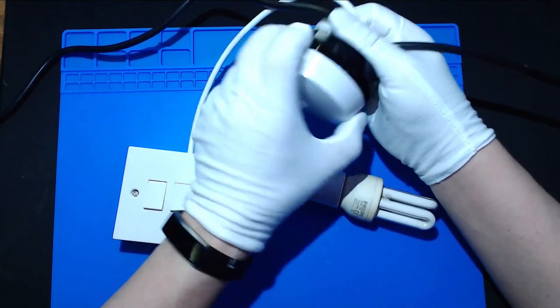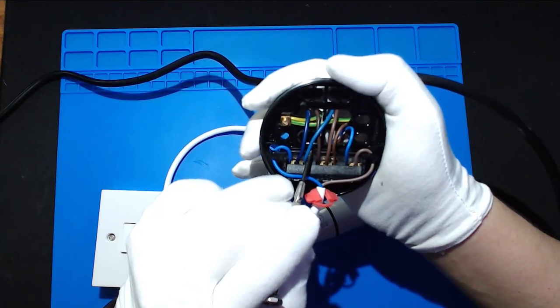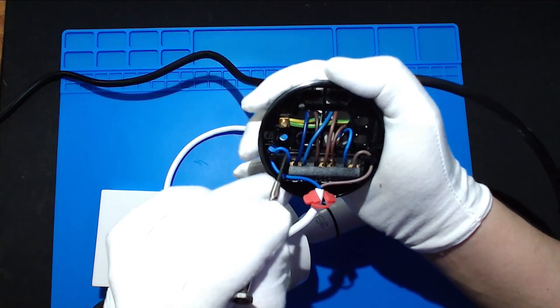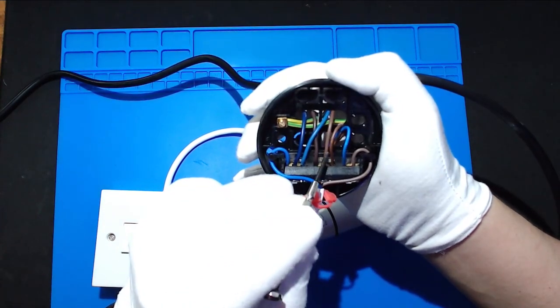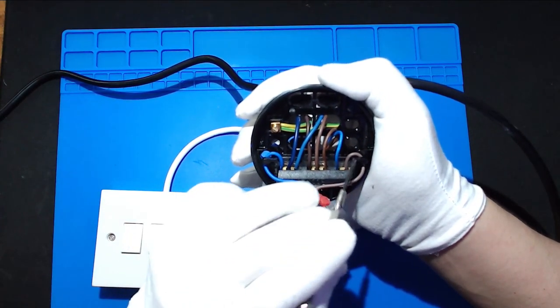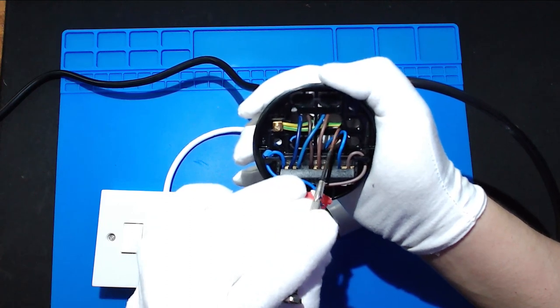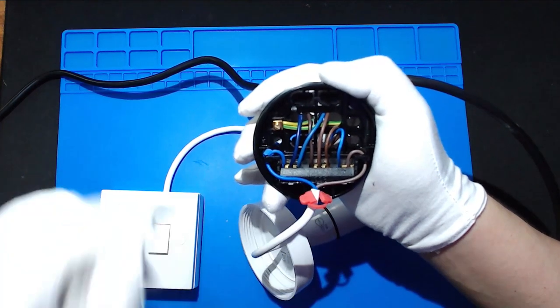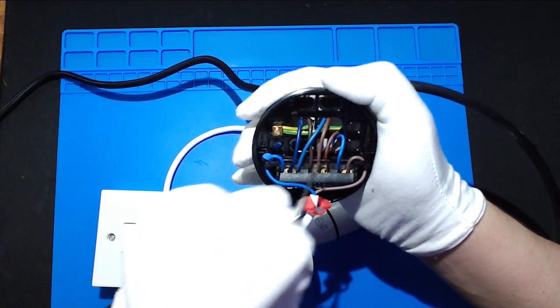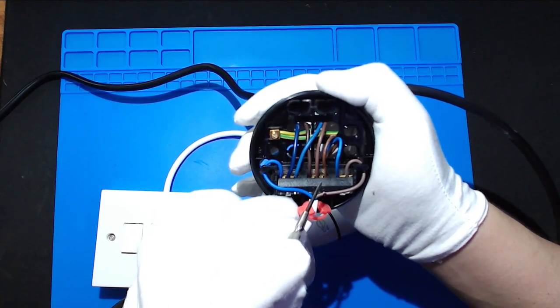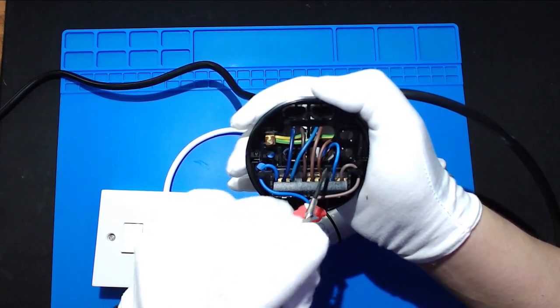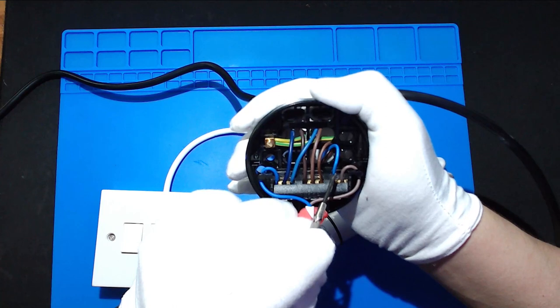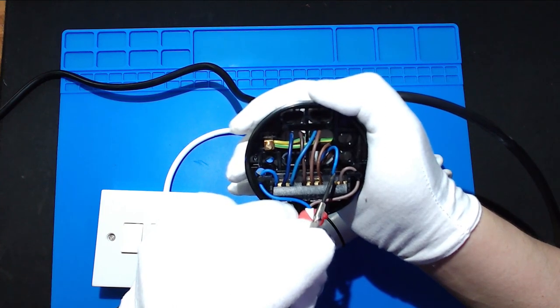So we want to unscrew the rose. Now inside here you'll see two neutrals coming in and one going out to the light. You'll see two lives coming in and one going out to light and a third one. The third one comes from your switch. Also from your switch is what's called the switch live. You should see this is marked somehow with a little bit of red tape or a little bit of red sleeving.